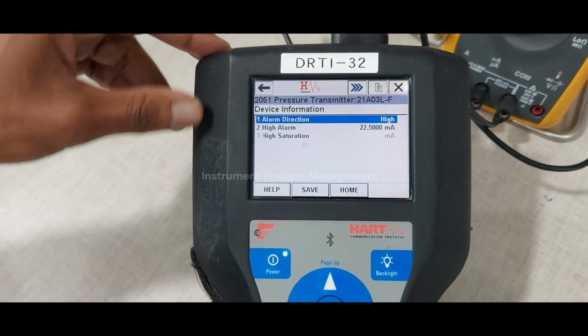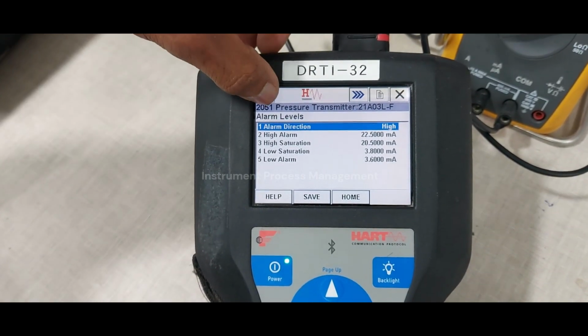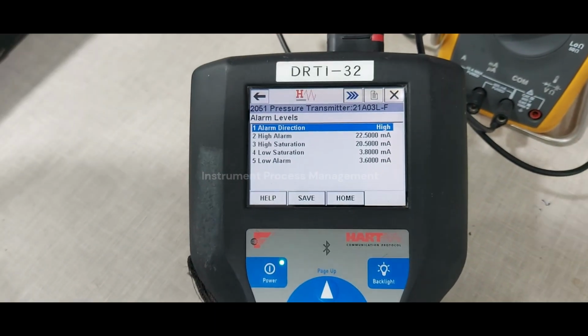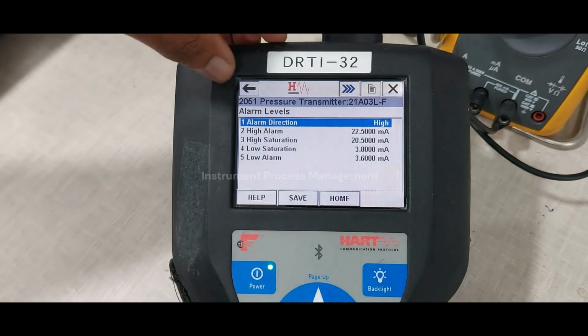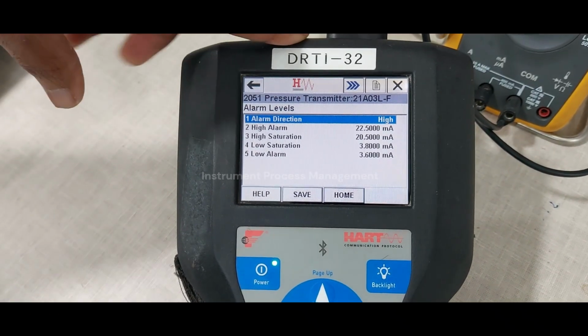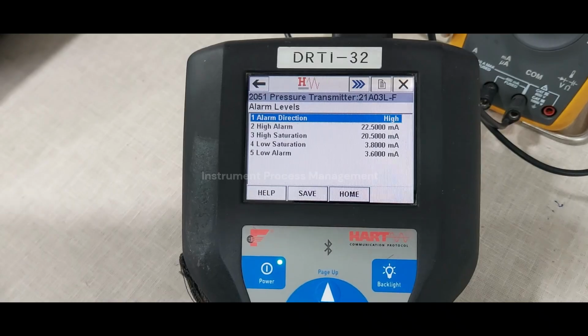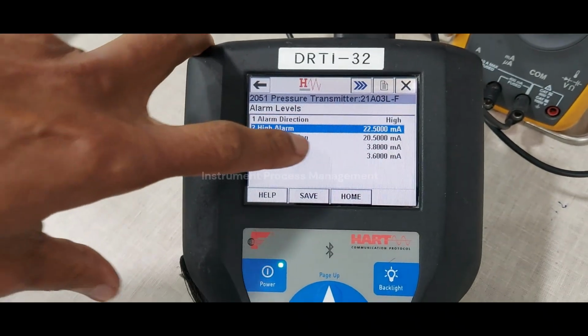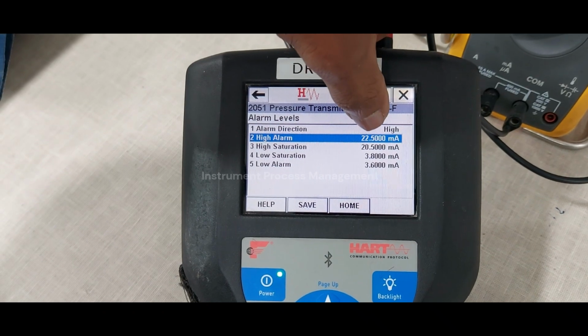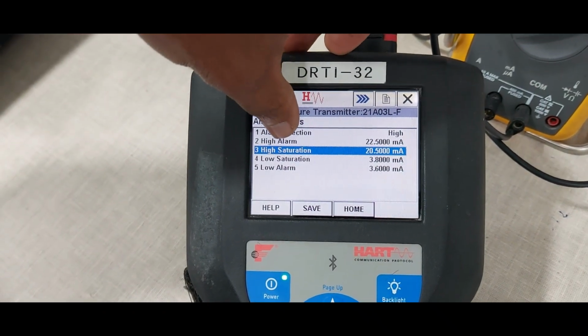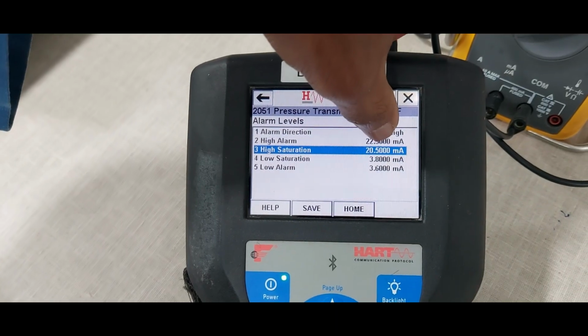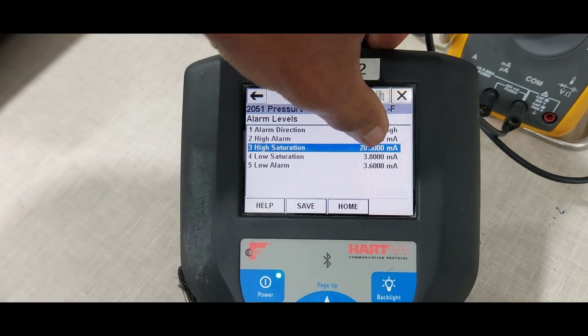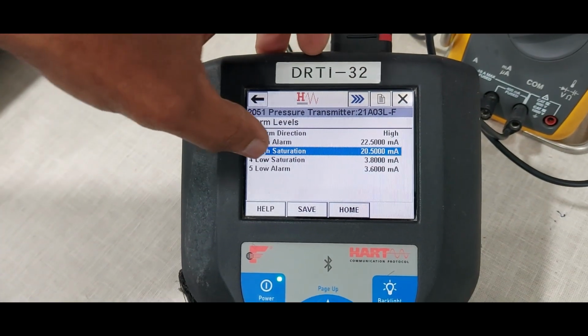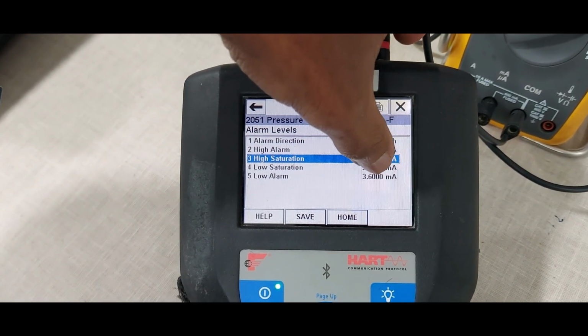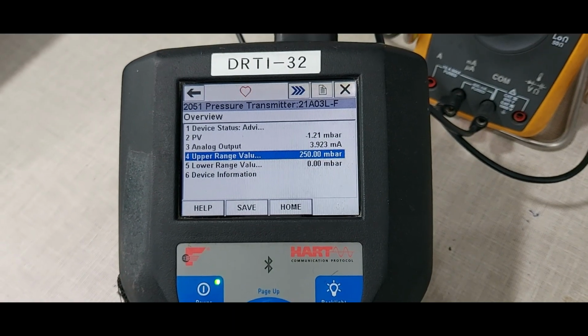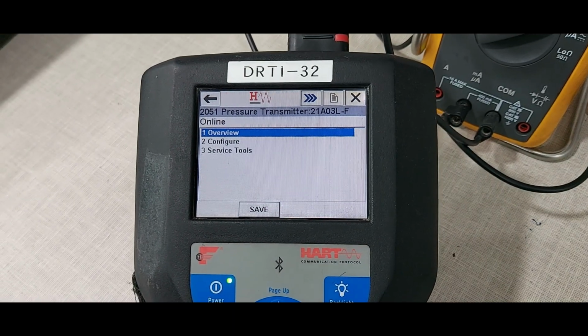We can check the alarm level also. Alarm direction is high. We can check the alarm direction. We can enable the dip switch from the transmitter. High alarm already assigned 22.5. High saturation level already assigned 20.5. Low saturation level already assigned 3.8 milliamps. Low alarm already assigned 3.6 milliamps. Next, back.